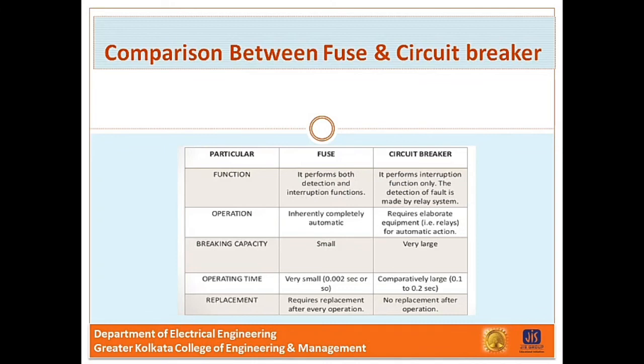Now, fuses only sense overcurrent or, to a degree, over-temperature and cannot usually be used independently with protective relaying to provide more advanced protective functions, for example, ground fault detection. Now, some manufacturers of medium voltage distribution fuses combine the overcurrent protection characteristics of the fusible element with the flexibility of relay protection by adding a pyrotechnic device to the fuse operated by an external protective relay.